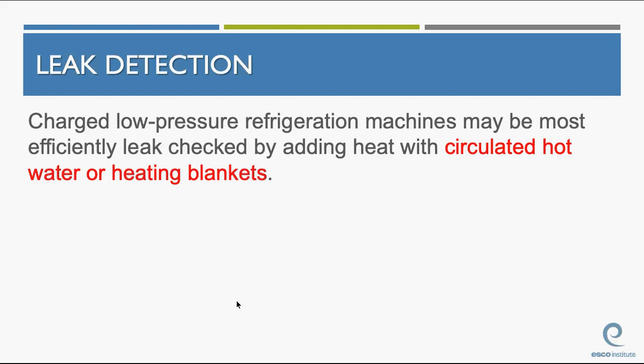Charged low pressure refrigeration machines may be most efficiently leak checked by adding heat with circulated hot water or heating blankets. If I heat the water circulating through it, or I put heating blankets onto the chiller barrel, I can raise the pressure of that refrigerant safely. Okay, and again, leak detection. This is going to be on your exam.